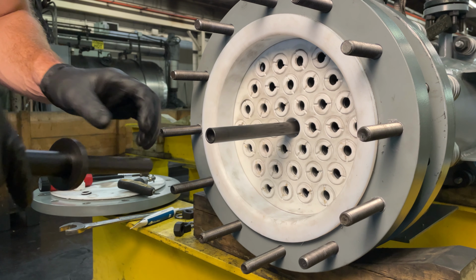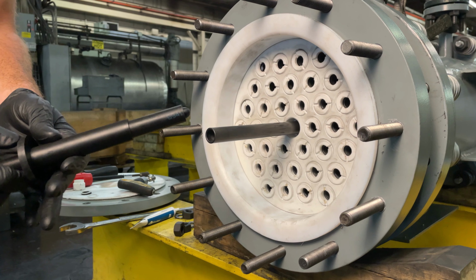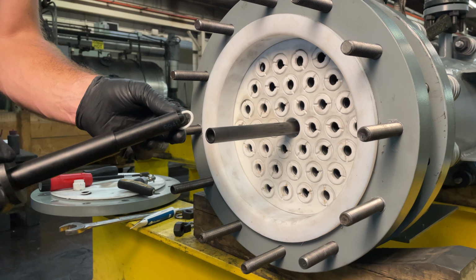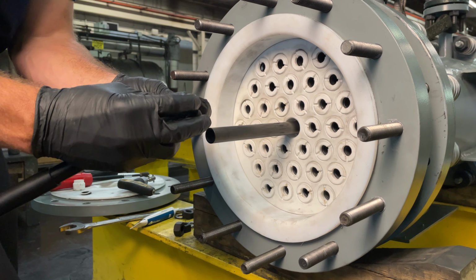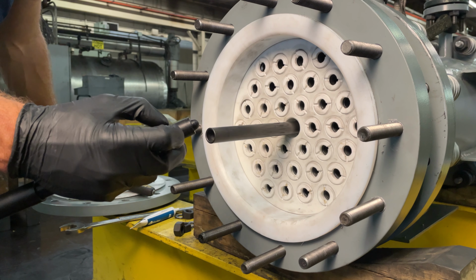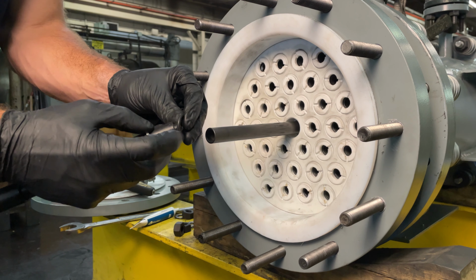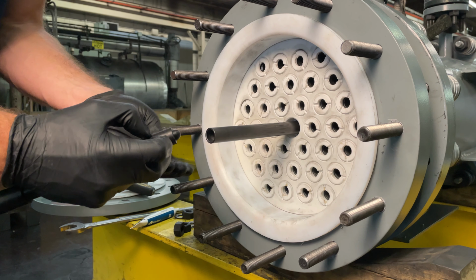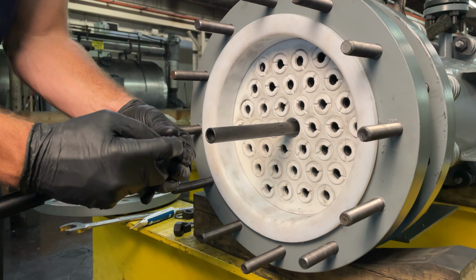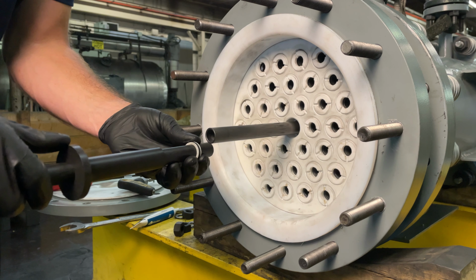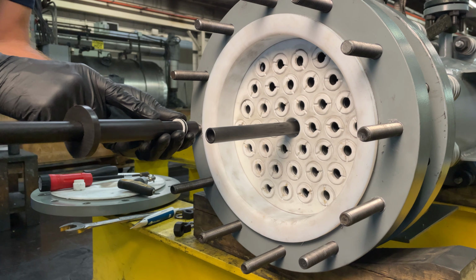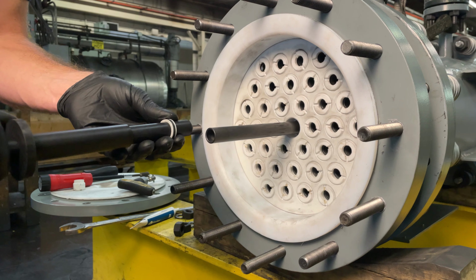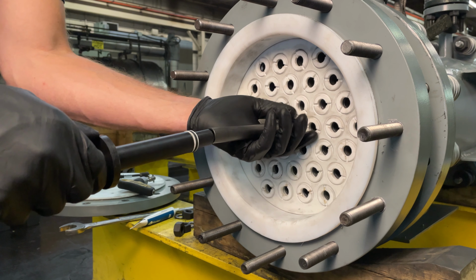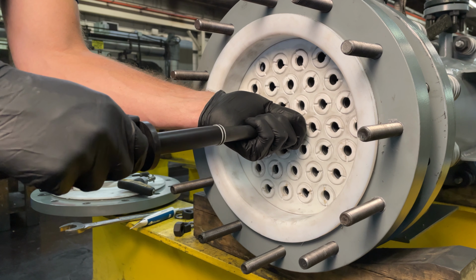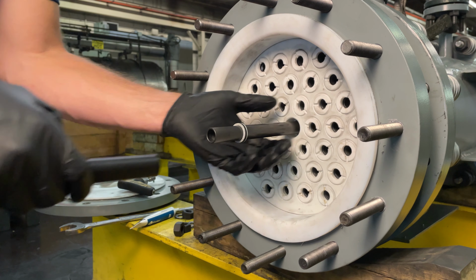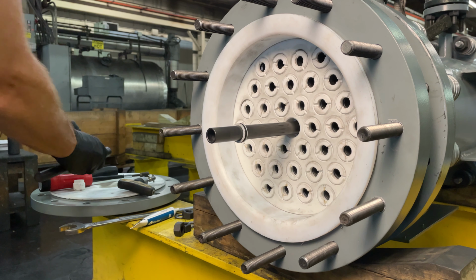Take your positioning tool, bevel side first, and apply a small amount of lubricant onto the backup ring, then the O-ring, and then finally another backup ring. Make sure the smaller diameter of the moving portion of the positioning tool is up against the backup rings, and then slide the rings onto the tube, leaving enough room for the tube nut to sit flush against the edge of the tube.